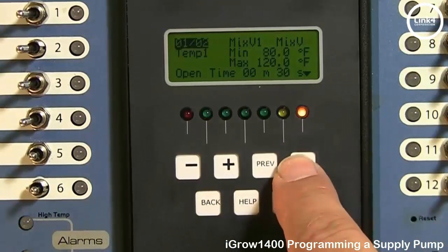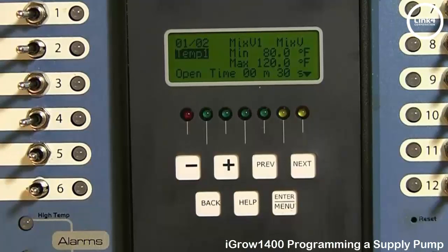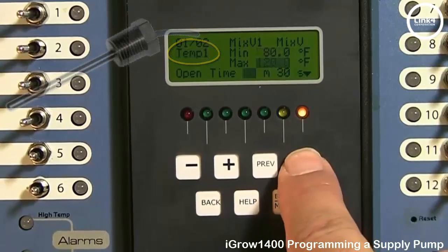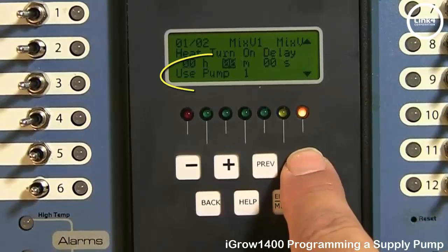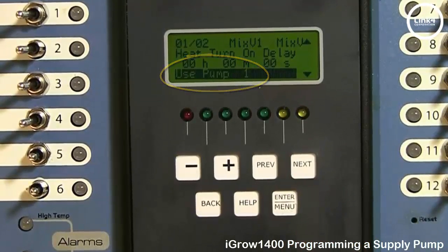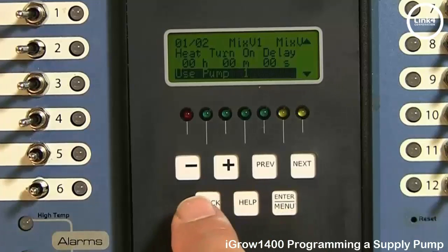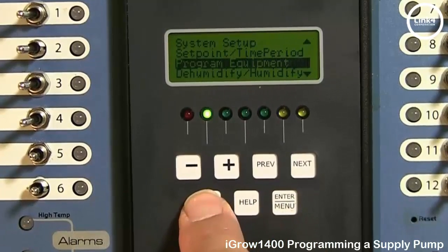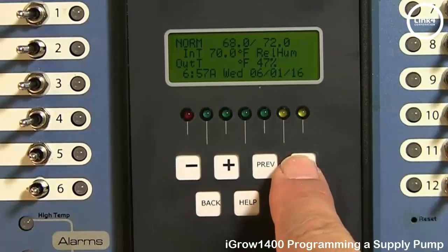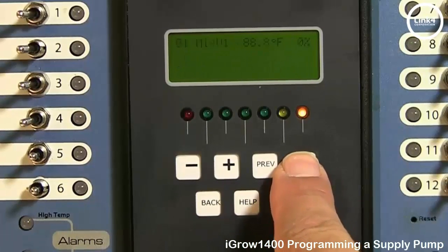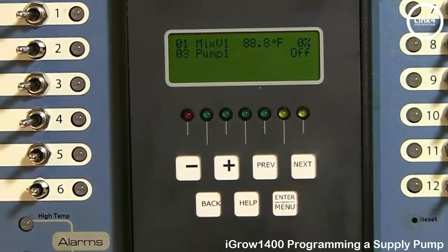And as you can see, this mix valve is associated with temperature probe 1, and it's also associated with pump 1. It's to use pump 1, the pump that we just programmed. And we're simply going to go ahead and hit back to get to the home screen, and then hit next, and then hit next again. And on this screen, this is our equipment status screen, and mix valve 1 is at 0%, and it's at 88 degrees Fahrenheit, and pump is off.